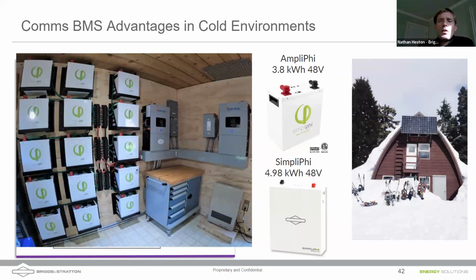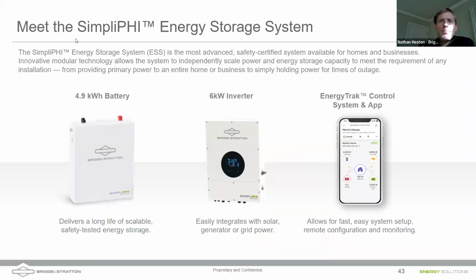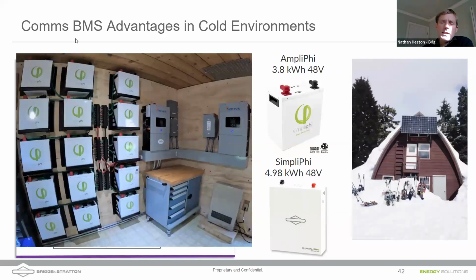So these batteries can operate at a greater range of temperatures, and I thought I had the temperature slide in here to explain that, but they can operate at a greater range of temperature. They just reduce that charging rate. So these can operate all the way down to negative 20 degrees Celsius. It slows down the charging rate at those temperatures. But eventually, because of the increased internal resistance at low temperatures, charging those batteries slowly at low temperatures raises the battery temperature, and that allows us to charge faster. There's a pretty unique solution with these communicating batteries.